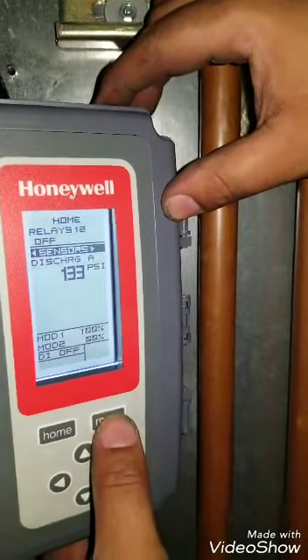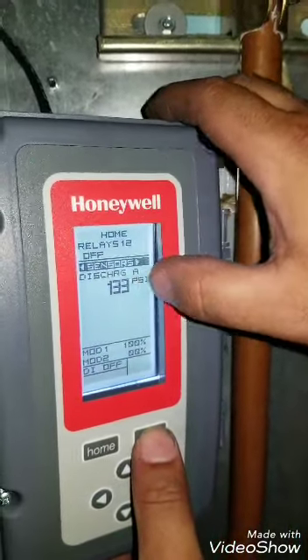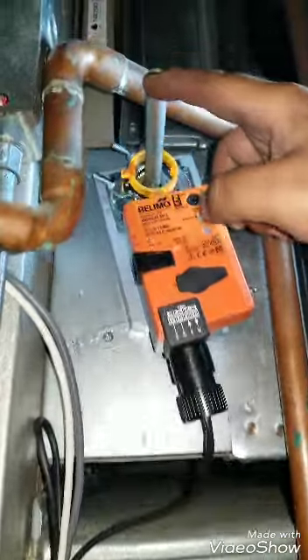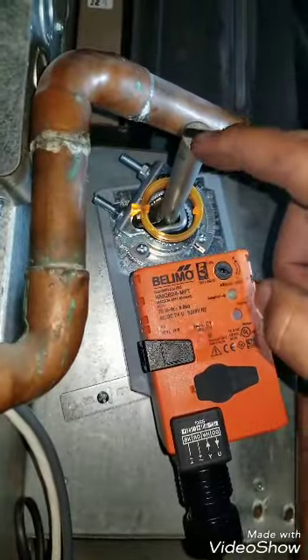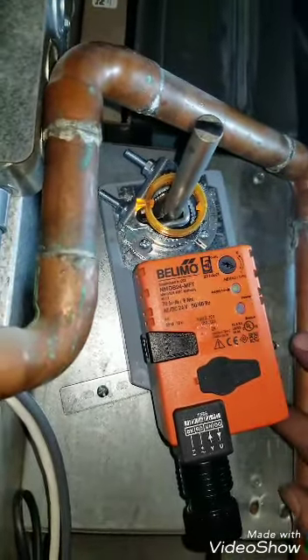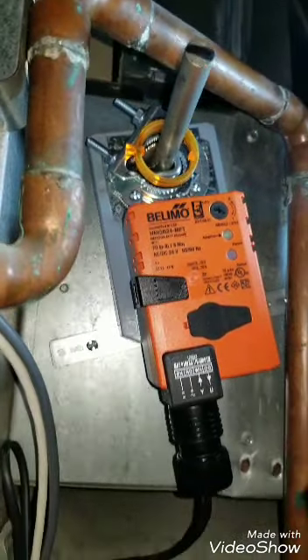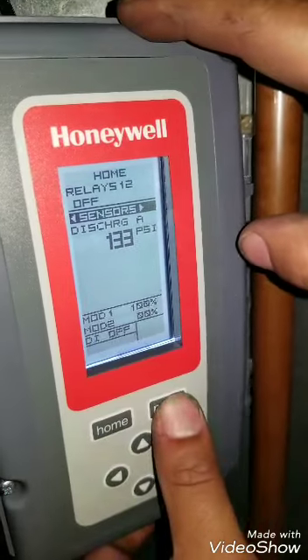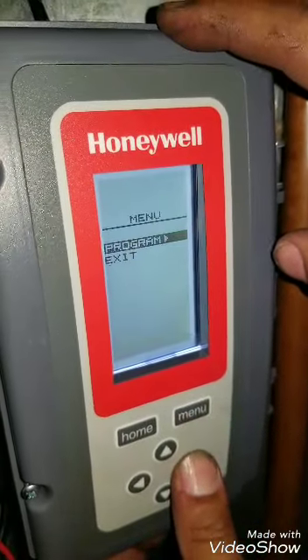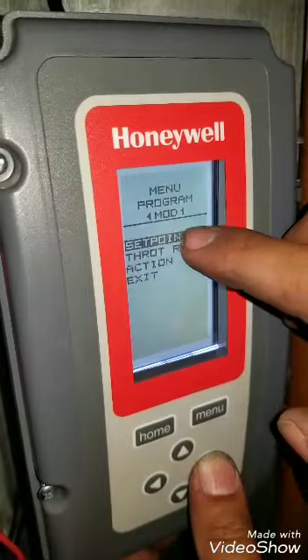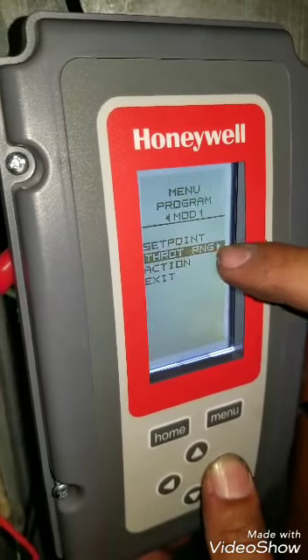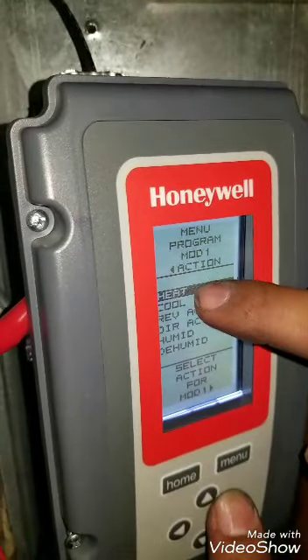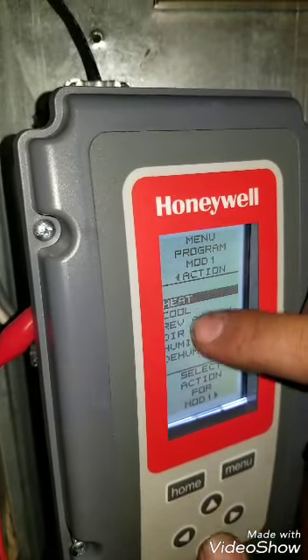All right, final step. Basically, you got 133 PSI. If you look up, you see how the Belimo is showing open. It shouldn't be open because you're trying to maintain 250 on the head. So right now, your damper should be fully closed. So how you get it to close is like this. Menu, program, mod 1. We said the set point was 250 with a 50 differential. And you go to action. It's either heat or cool. You can put it for heat or cool. Right now it's in heat. Watch what happens when I put it in cool.